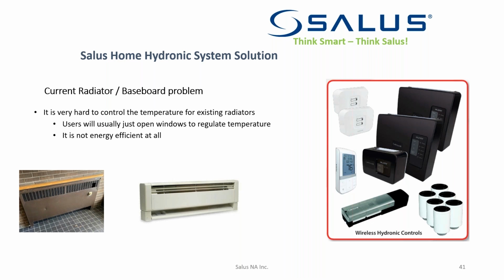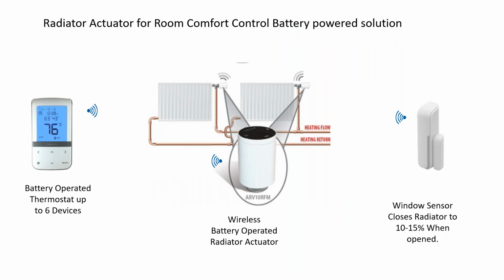And currently there's a problem in a lot of our buildings where it's very hard to control the temperature from a radiator. And users, or your tenants, will generally just open windows to regulate temperature, which is horrible. It's not energy efficient at all. Steam systems have the same exact problem. So what Salus has come out with is a kit where we integrate a wireless thermostat and a wireless battery operated actuator and window sensors to all work together to control the system flow through the radiators, and based on comfort, not just based on pressure as some systems run right now.